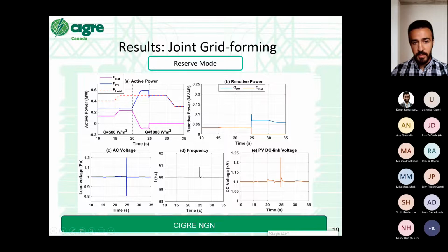Close to 25 seconds, the battery energy storage system here trips, and the PV, in response, is going to take over the grid forming task and starts providing the required active and reactive power generation.